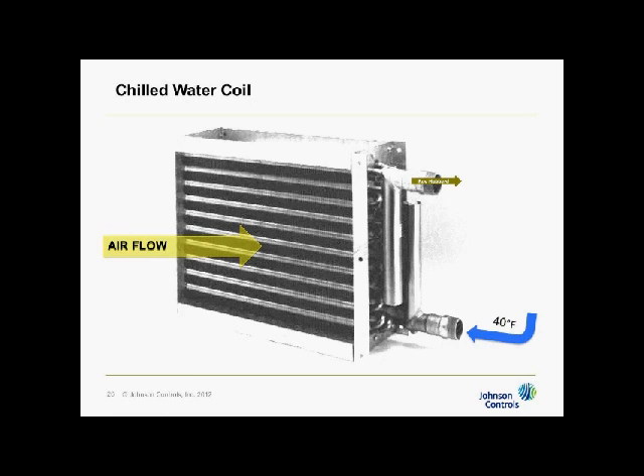And if you recall from my formula earlier on, load is equal to flow times delta T everywhere. So if my load hasn't changed on the coil, then my flow has gone up. My delta T has to come down.